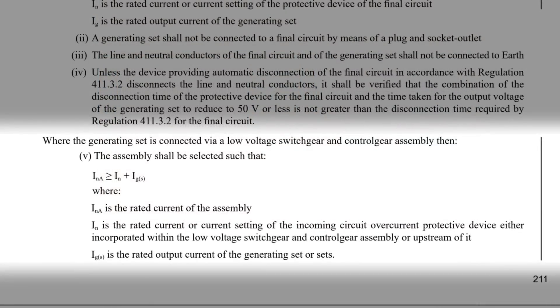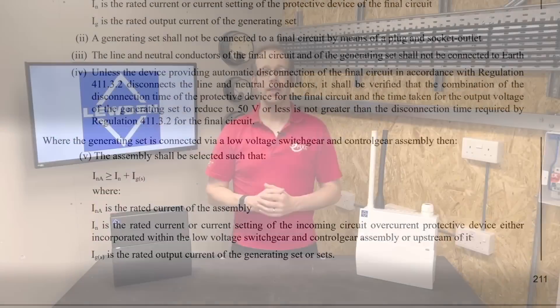The regulation reads: where the generating set is connected via a low voltage switchgear and control gear assembly — which is what we do in pretty much every case of PV installation — then the assembly shall be selected such that INA ≥ IN + IGS, where INA is the rated current of the assembly. So let's break that down a little bit. INA is the rated current of the assembly, or in other words, how much current the consumer unit can have flowing through it.